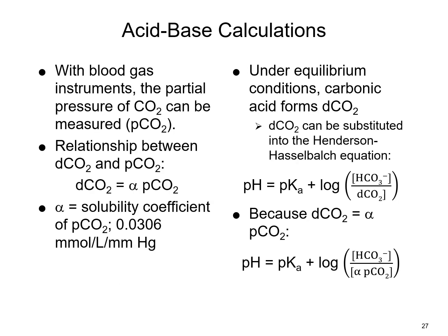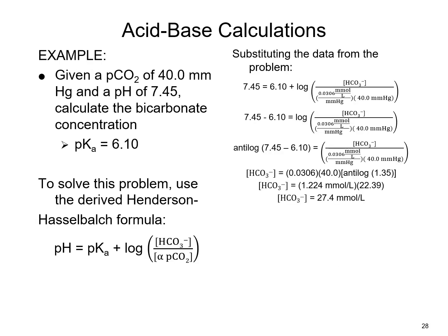Blood gas instruments measure the partial pressure of CO2 as pCO2. There is a relationship between dCO2 and pCO2 involving the solubility coefficient of pCO2. Under equilibrium conditions, carbonic acid forms dissolved CO2, and dCO2 equals the solubility coefficient times pCO2. Plugging this in gives an equation for pH. In practice, we can use the measured pCO2 and pH values to calculate the bicarbonate concentration for a patient sample.